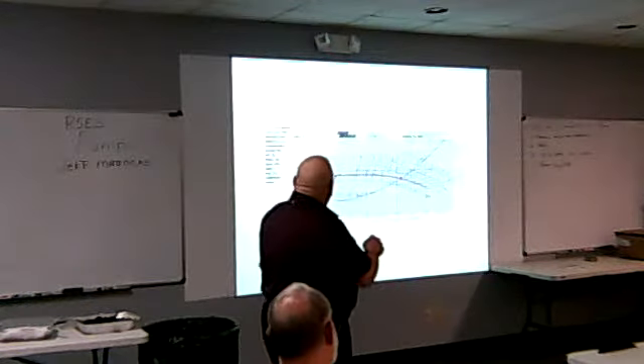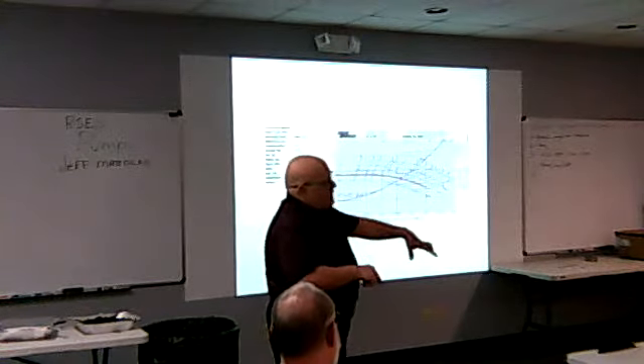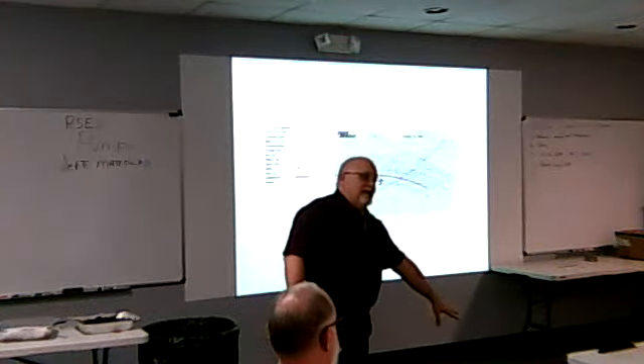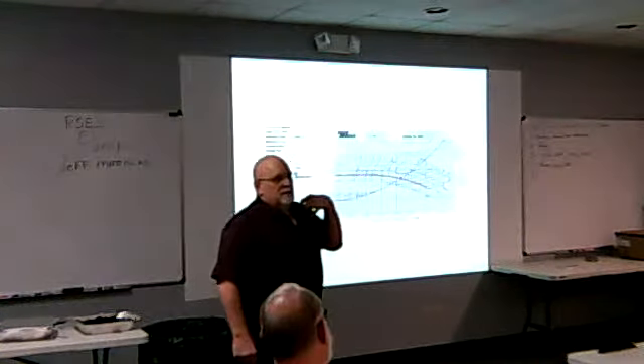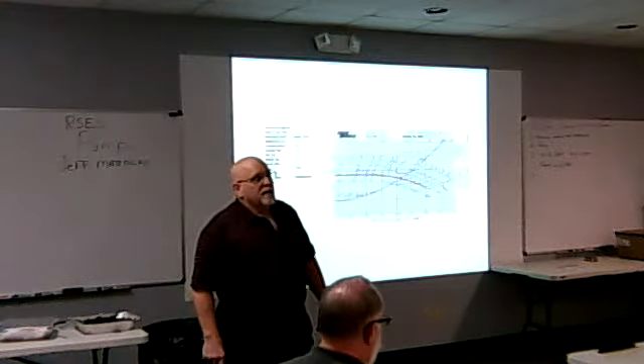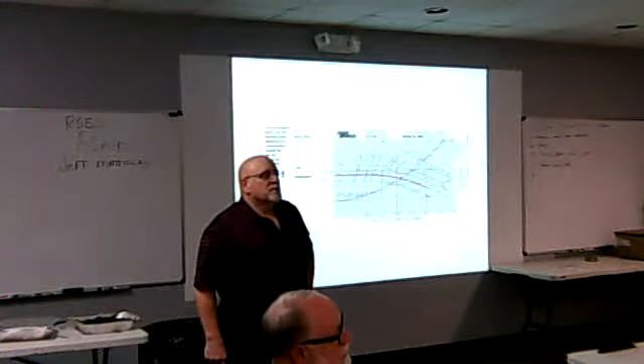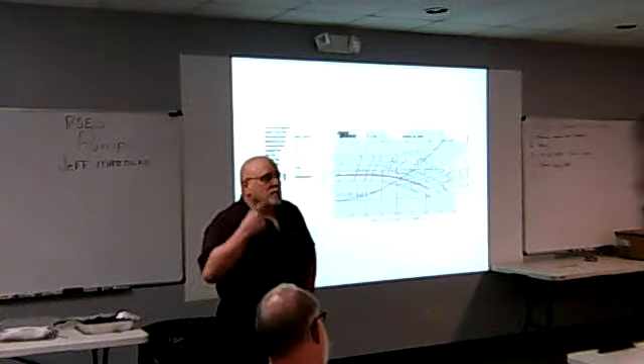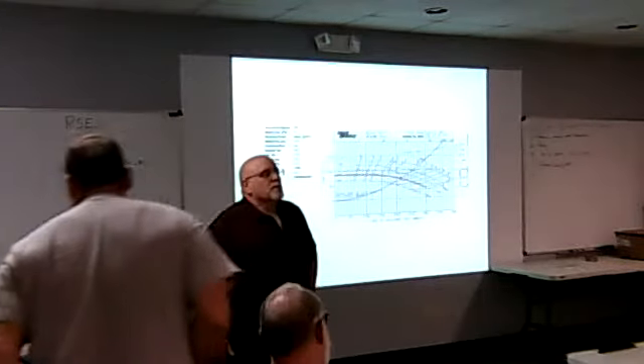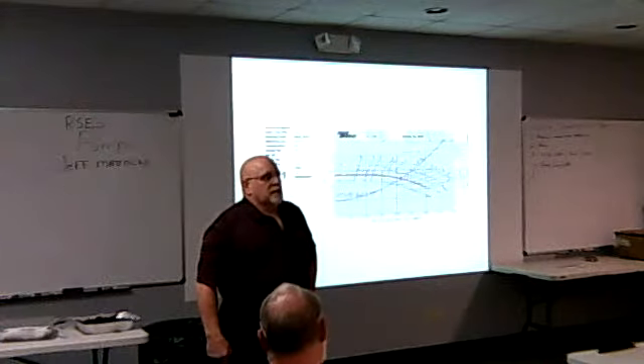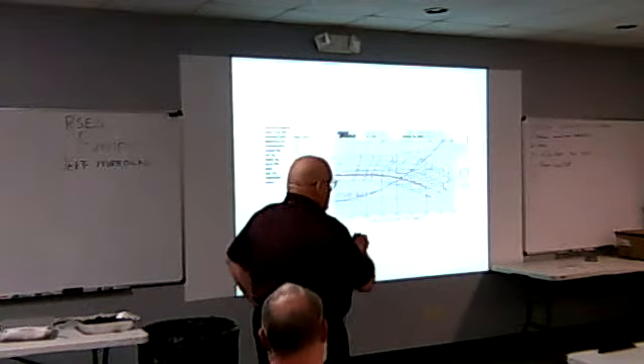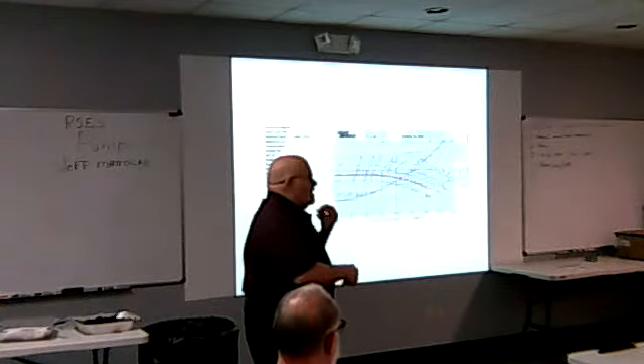If I've got a cooling tower that's 6 feet below, you have your atmospheric pressure, minus your friction, plus or minus your elevation, minus your vapor pressure. That tower is 8 feet down. I have to lift that. That's going against my NPSH. So that positive suction head, that's temperature specifically you're working through, right? And you have different charts for different temperatures? Correct. Yeah, because if you notice when we do these, it's not so much the difference in temperature.